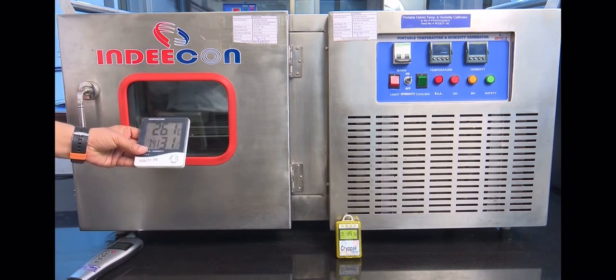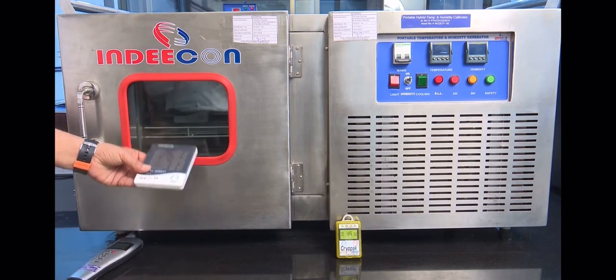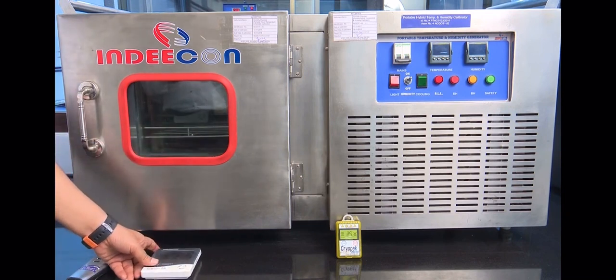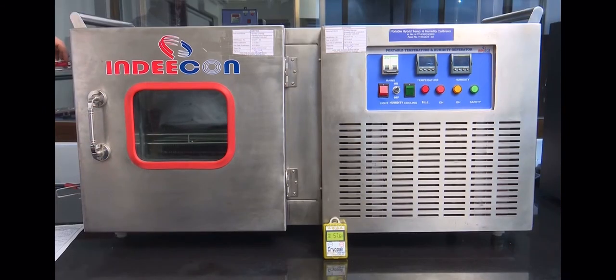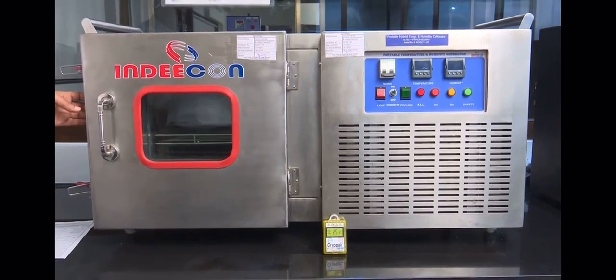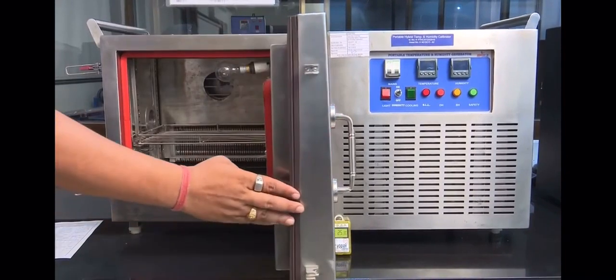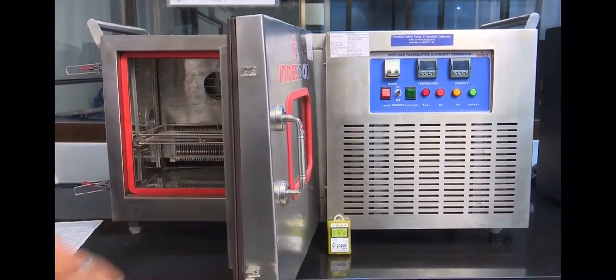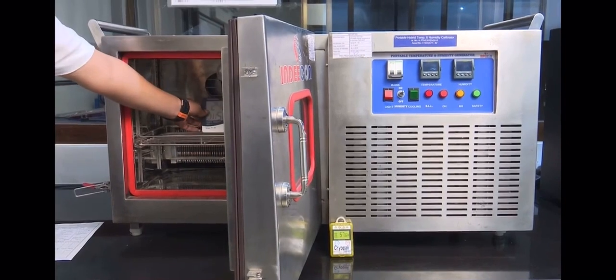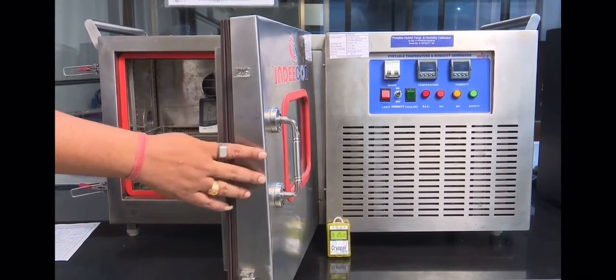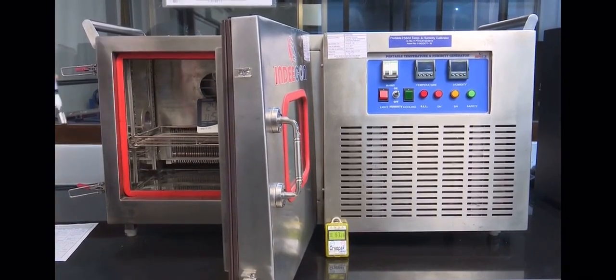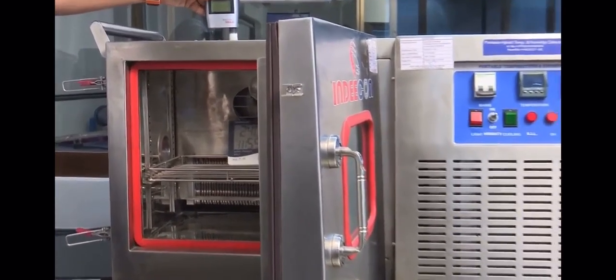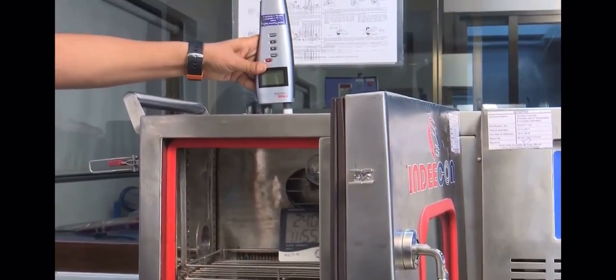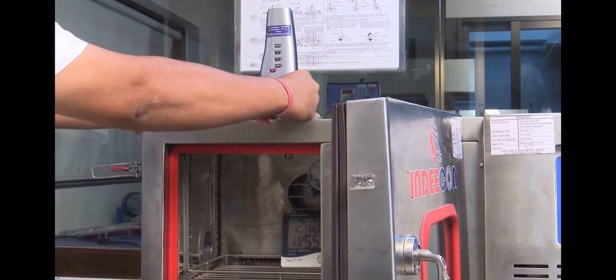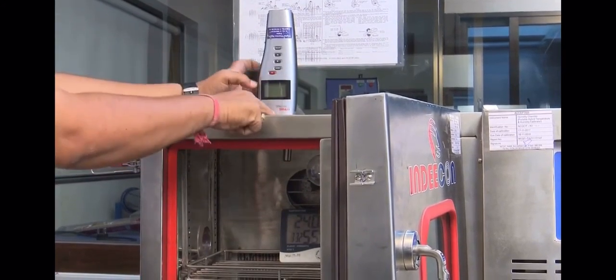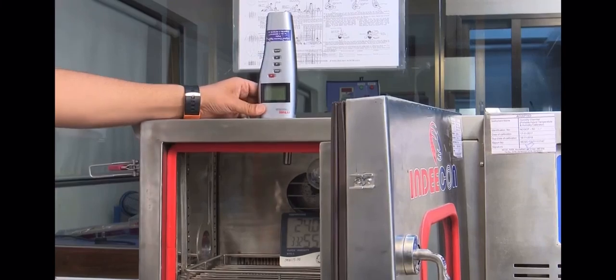Now I am starting calibration of this digital thermohygrometer. First of all, open the door. Then put the UUC in the environment chamber. Now insert thermohygrometer to environment chamber properly without any leaks from its insertion point. Ensure that the door is in locked position.